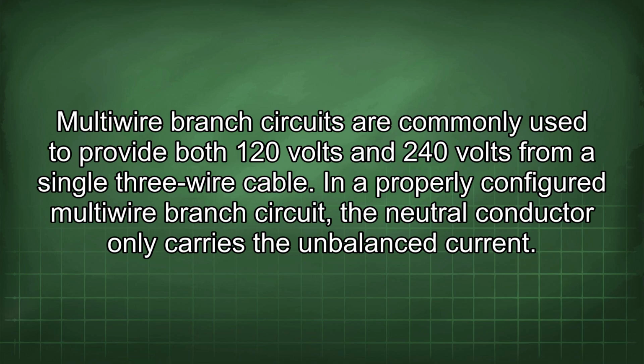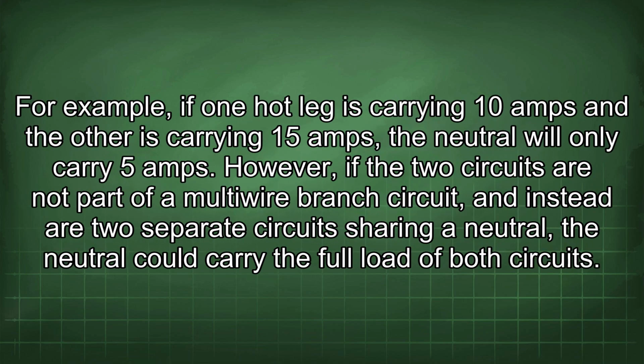Multiwire branch circuits are commonly used to provide both 120 volts and 240 volts from a single 3-wire cable. In a properly configured multiwire branch circuit, the neutral conductor only carries the unbalanced current. For example, if one hot leg is carrying 10 amps and the other is carrying 15 amps, the neutral will only carry 5 amps. However, if the two circuits are not part of a multiwire branch circuit and instead are two separate circuits sharing a neutral, the neutral could carry the full load of both circuits.